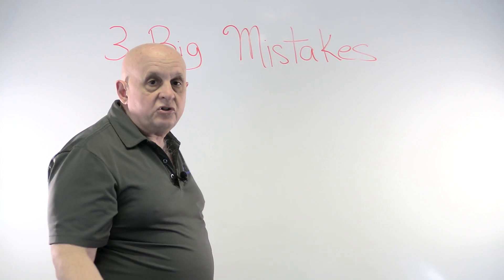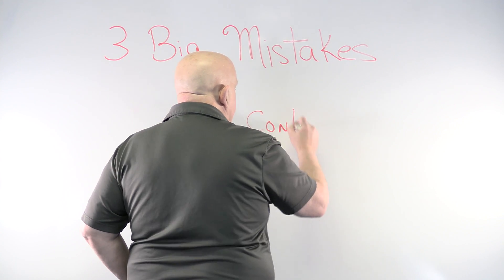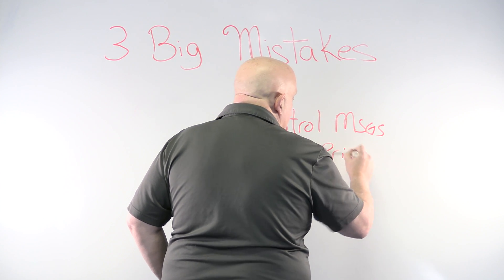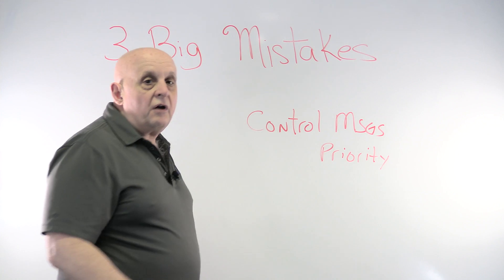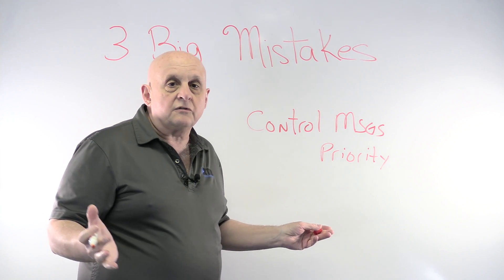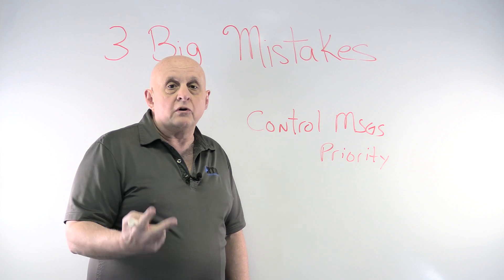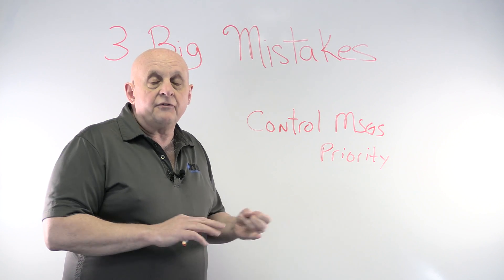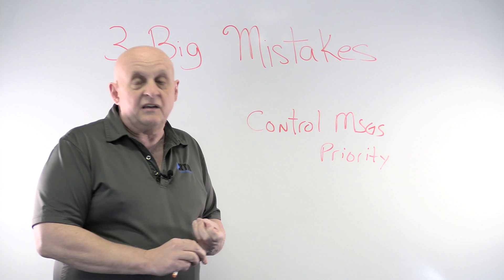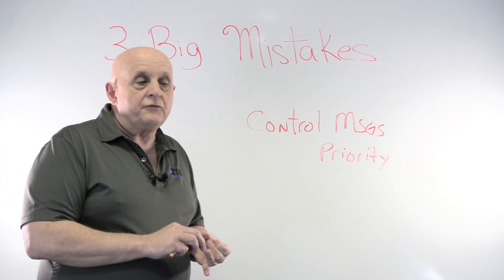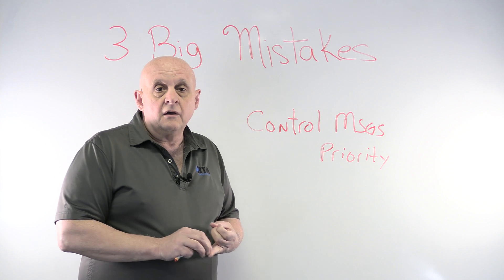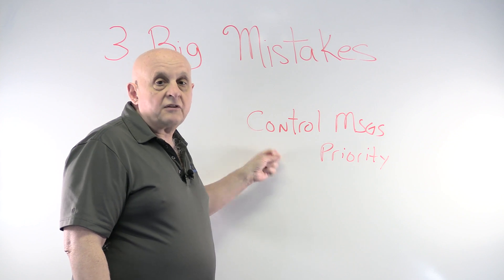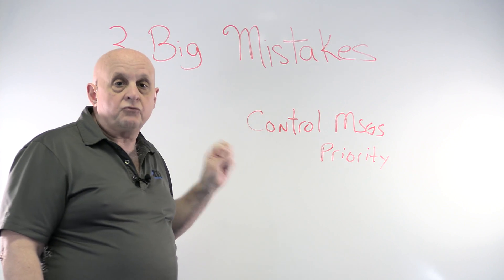Mistake number two is not giving control messages priority. Control messages need to get priority all the time, no matter what. Generally you need two priorities on an Ethernet IP network: your control messages get the highest priority, everything else gets a lower priority. If you have IoT traffic or any cyclic traffic on the network, that has to be subjugated so that control messages get through before anything else.